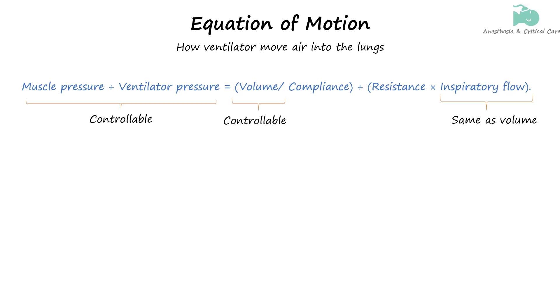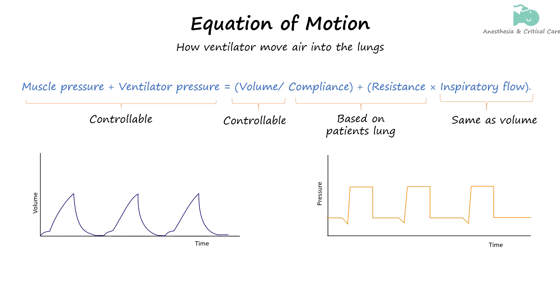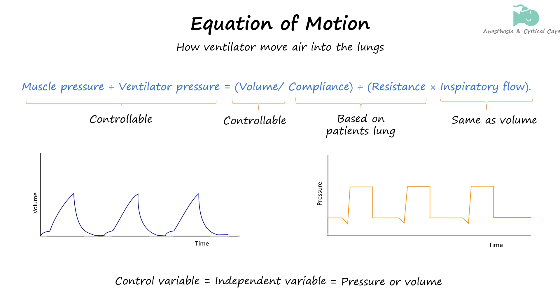The rest of the parameters on the right side of the equation are determined by the patient's respiratory conditions. So ventilators can be seen as devices that shape the pressure or volume waveform. We call pressure or volume the control variable, or independent variable, because it remains constant despite changes in lung compliance or resistance. The other variable, which changes in response, is the dependent variable. To determine the control variable, we identify which one stays constant.